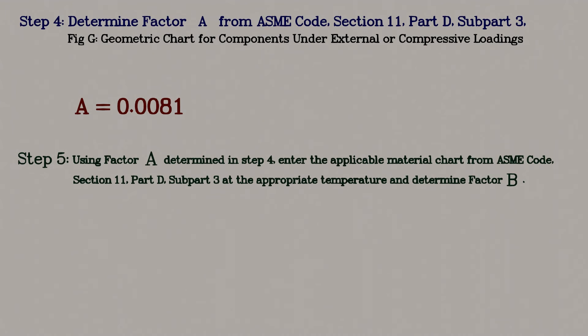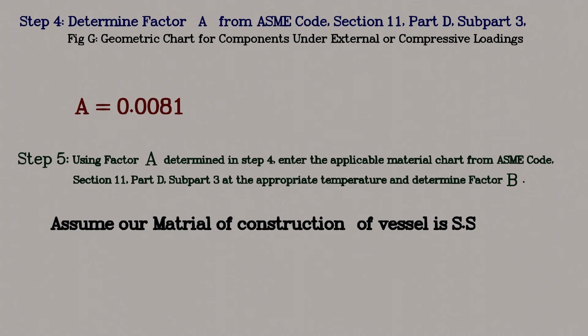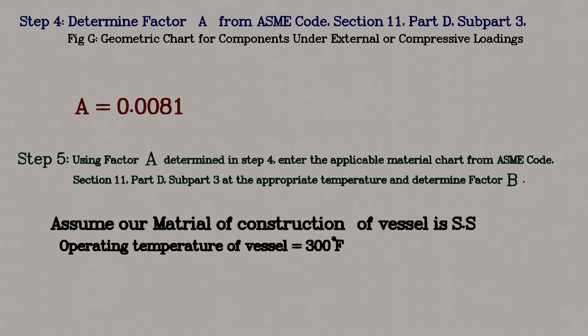In step 5, we calculate the value of B. To do this, we need the material of construction, the operating temperature, and factor A. Assuming the material of construction is stainless steel and the operating temperature is 300°F, using these data we find B = 11,800.